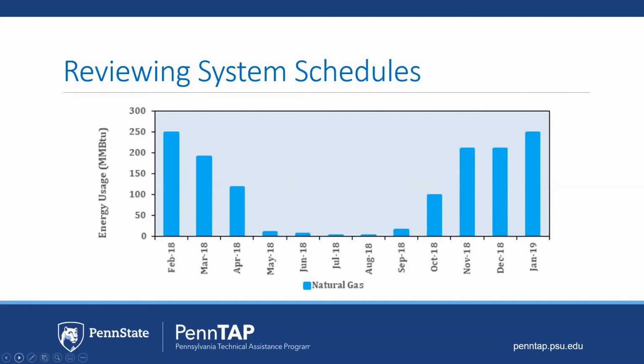At their facility, they had a heat pump and extra Reznor heaters throughout the facility as supplemental heating. It was suggested that if they could hold off and start the boiler maybe in mid-November and then turn the boiler off in mid-March, the facility could save up to $2,600 per year in natural gas consumption. Since there are limited preparations in making this change, this would be an immediate savings for the year.